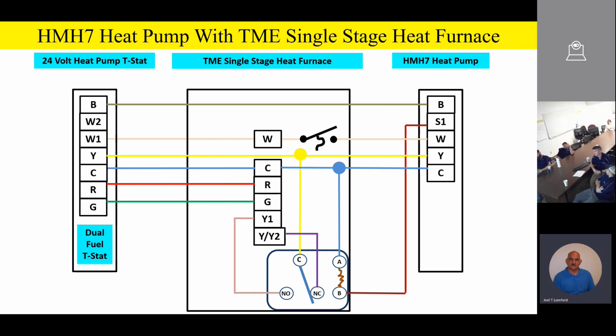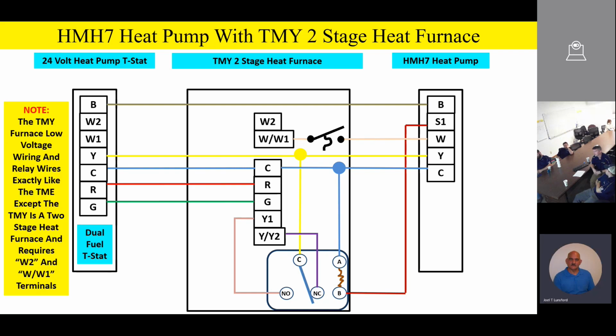All right, so the TMY furnace, the TMY is a two-stage heat. Now you're going to notice something. The TMY furnace, the low voltage wiring and relays and all, it wires exactly like the TME. The only difference is the TMY is a two-stage heating furnace and requires a W2 and a W/W1 terminal. So let's go ahead and wire that in.